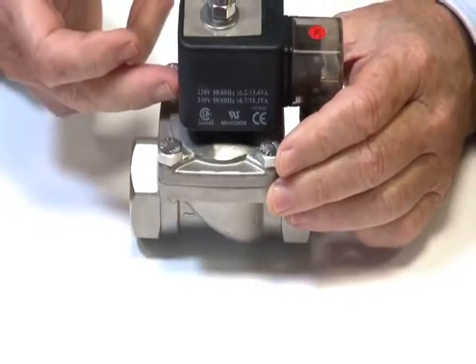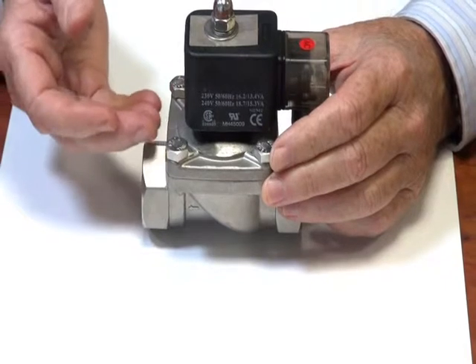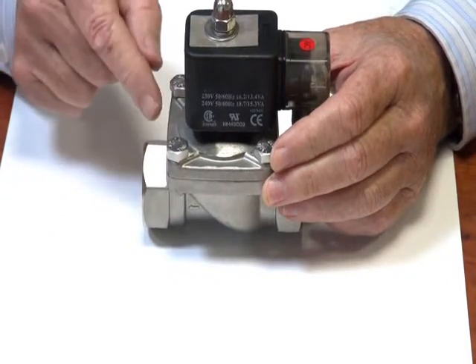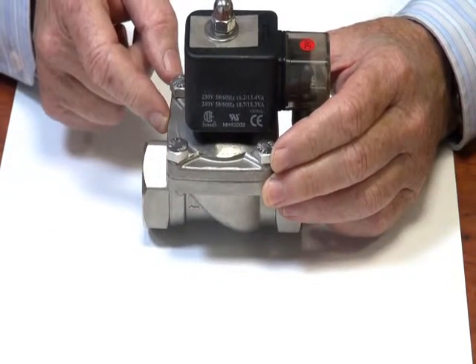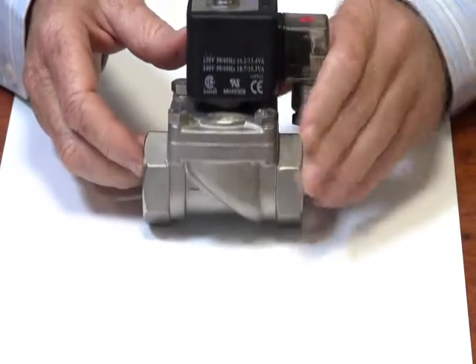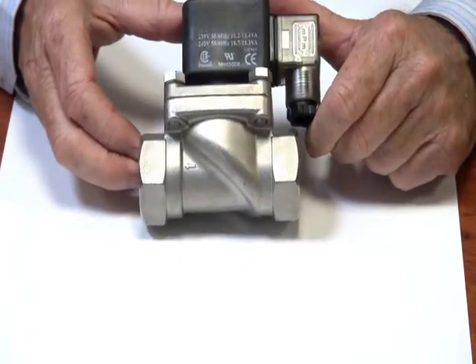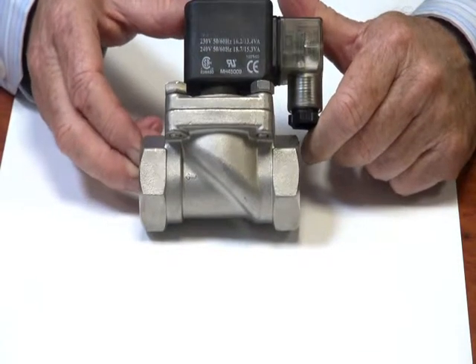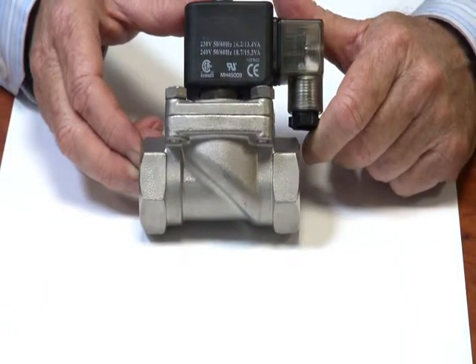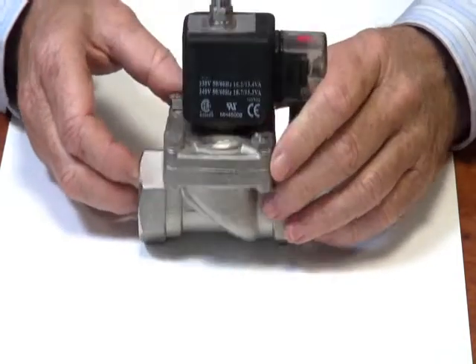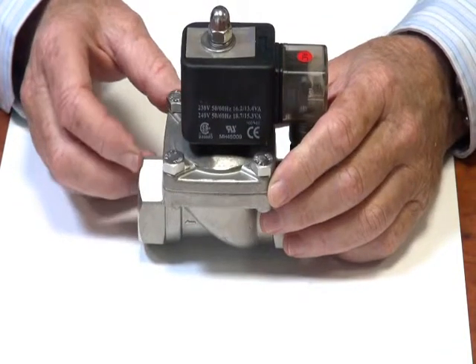When the power is operated on this valve it lifts the armature. The armature is coupled to the diaphragm so this valve can be used on applications right down to draining a tank. It'll open up when there's no pressure. It doesn't require any differential to make it work and it is a coupled diaphragm or zero differential valve.